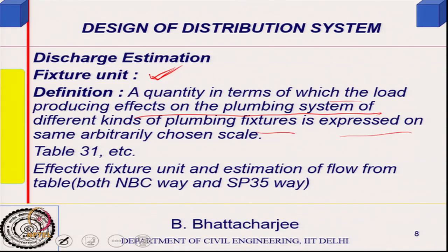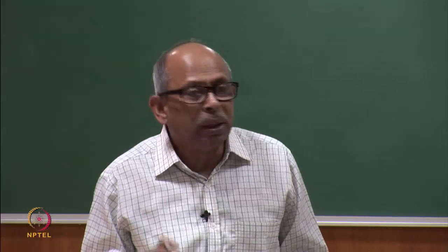For example, a wash basin tap might be one fixture unit and a shower might be two fixture units. You bring in all your load expressed in terms of fixture units — it is the load-producing capacity of different fixtures expressed in a uniform unit. This is given in Table 31 of SP 35 for different types of fixtures.